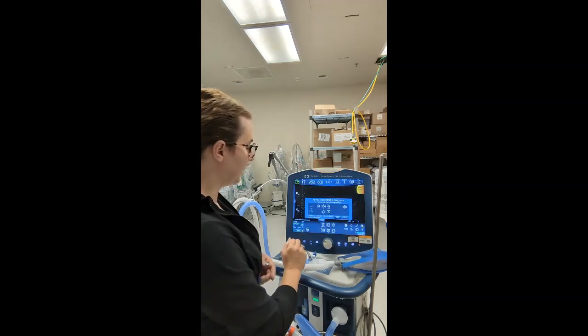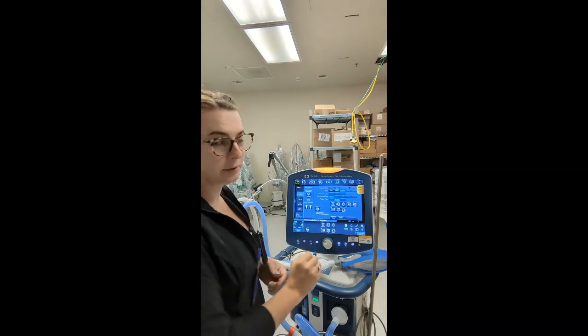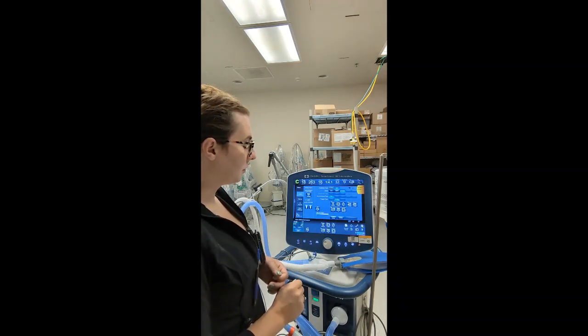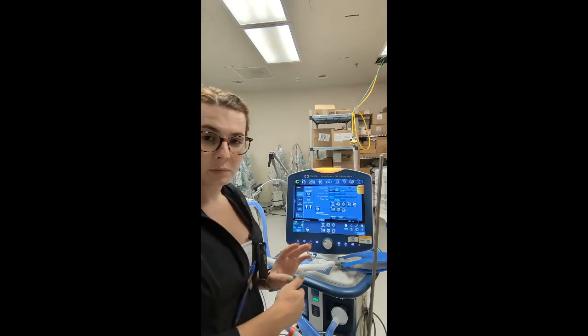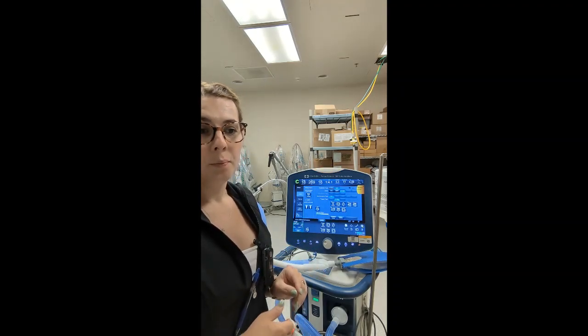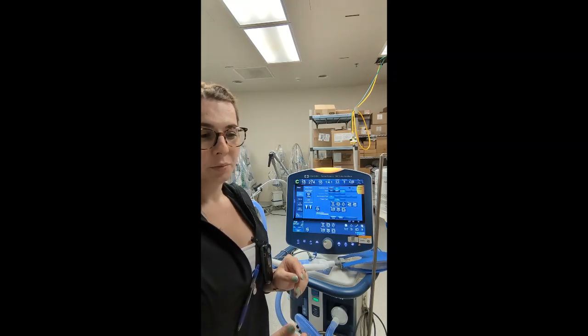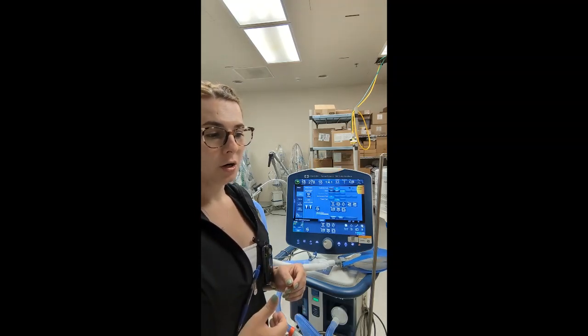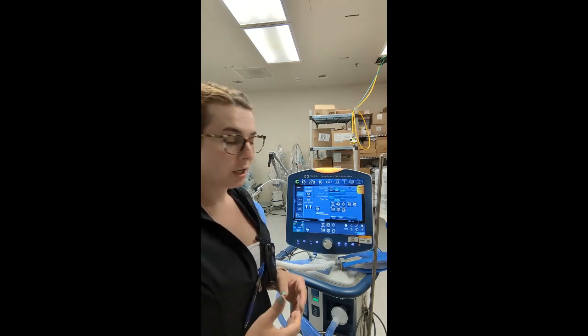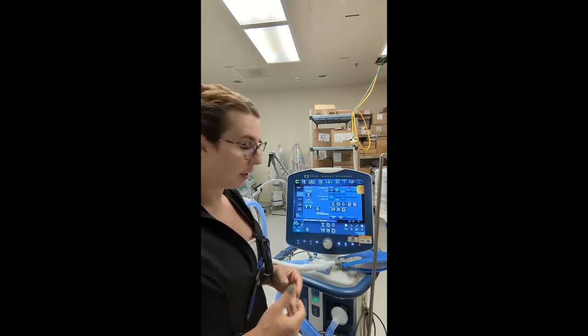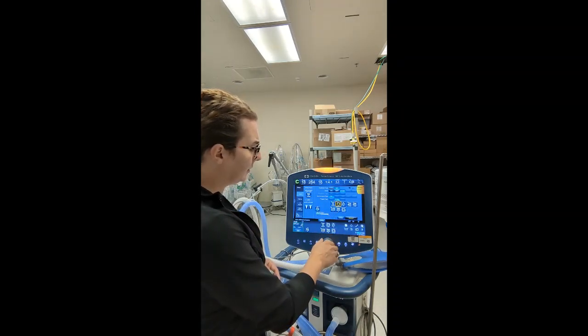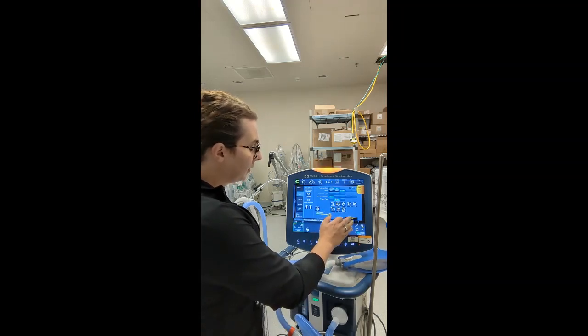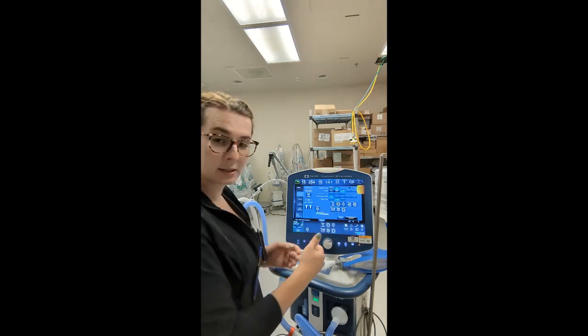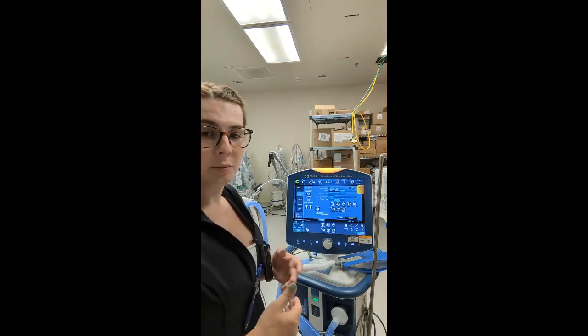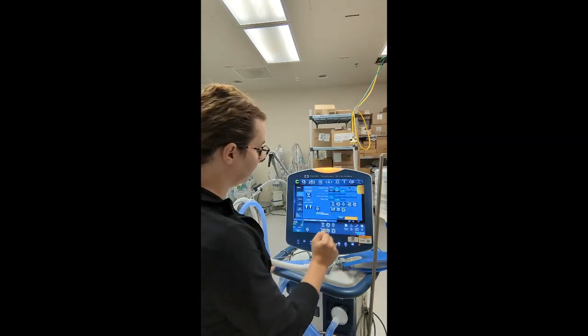Next, we also want to change our sensitivity. Because we're on a ventilator, sensitivity is usually really low, but in a non-invasive mode with positional changes, coughing, or just asynchrony, we want to change the sensitivity of our triggering. So we're going to put it between 8 and 10. Now this is patient dependent, so if 8 or 9 is not working, keep going up. And unlike the Draeger, it is opposite. The higher the number, the less sensitive, whereas on the Draeger, the higher the number, the more sensitive.